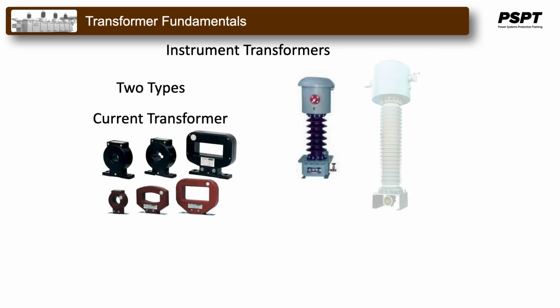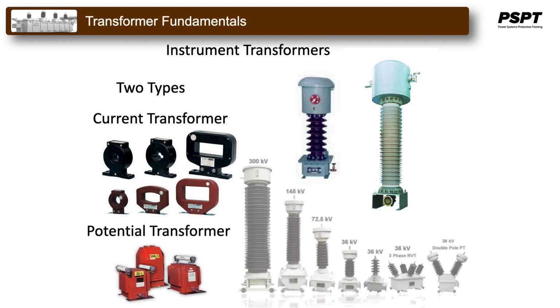Such transformers are of two types. Current transformers. Current transformers are used when the magnitude of AC current exceeds the safe value of the current required for the measuring instruments. Potential transformers or voltage transformers are used where the voltage of the AC circuit exceeds 750 volts and it is not possible to provide adequate insulation on measuring instruments for voltage more than this.